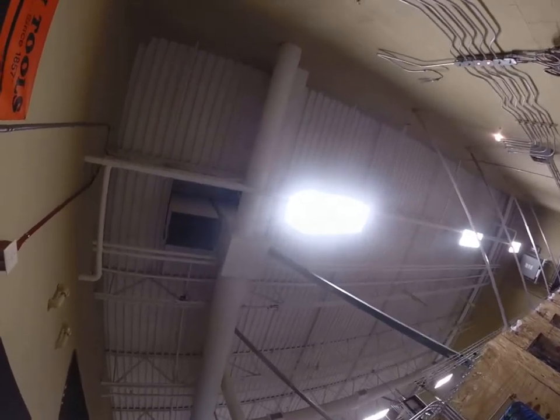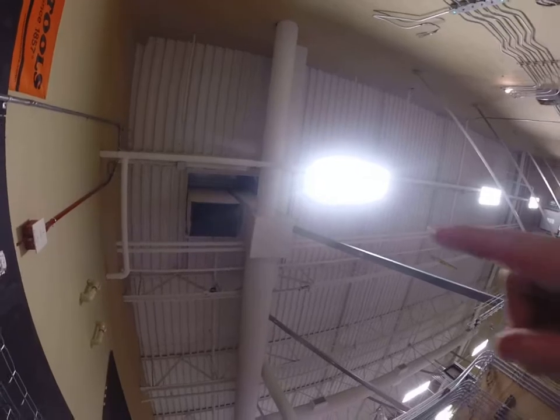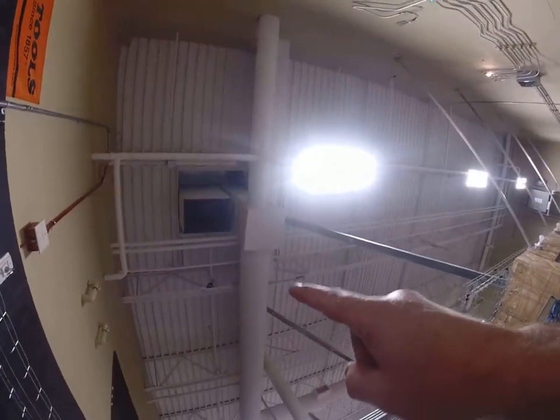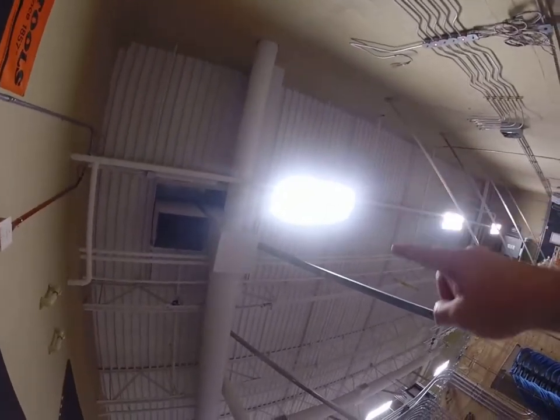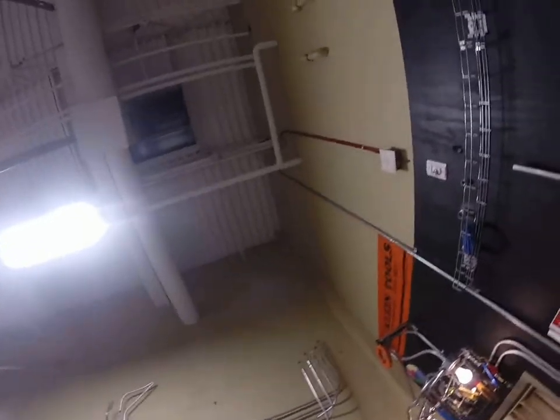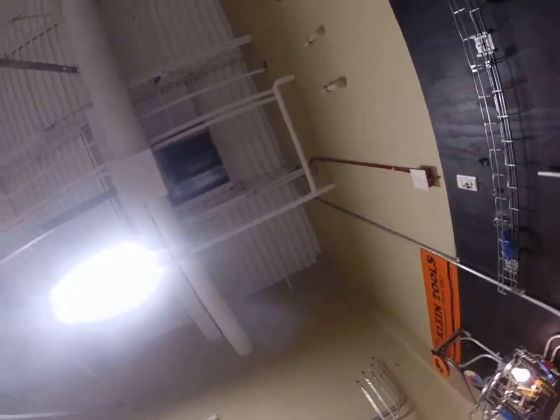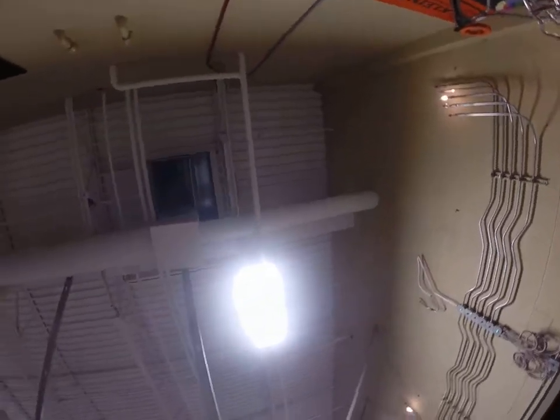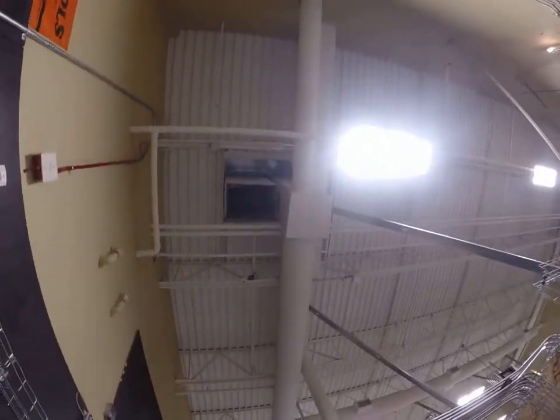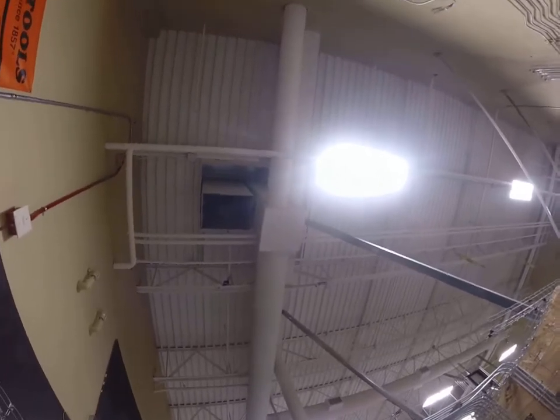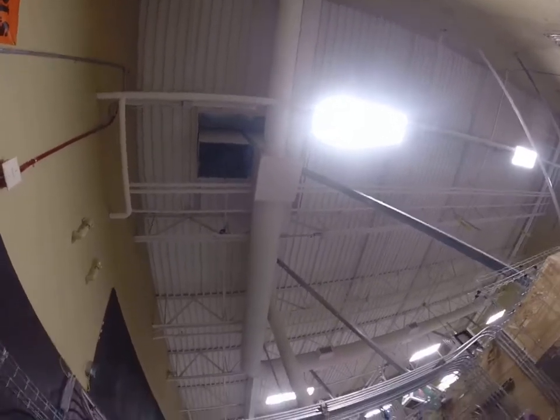Before I zoom away from this, I also want you, if you can, to take a look next to that return. You can see that there's a lot more steel structure around that ductwork. And probably turn it this way and you can kind of see there's more solid steel around there. Anytime you see that penetration in the roof with that framing of steel around, you can guarantee that that's where one of your rooftop units is going to be set.